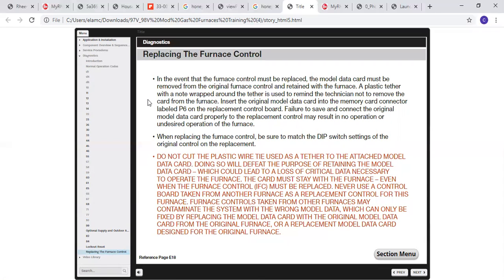So if you ever have to replace the circuit board, the control board, the model data card must be removed from the original control. There is a zip tie there. It's tethered there for a reason, so you have to take it out in order to change the board. Failure to save and connect the original data card properly to the replacement board may result in no operation or undesired operation. When replacing the furnace control, be sure to match the dip switch settings of the original board. If you're using the EcoNet, you don't have to worry about that. Do not cut the plastic wire tie that tethers the model data card. Doing so will defeat the purpose of retaining the model data card.